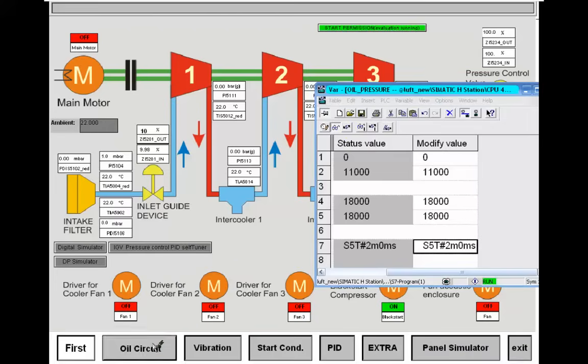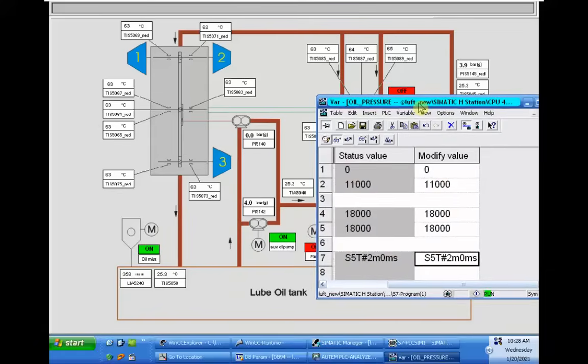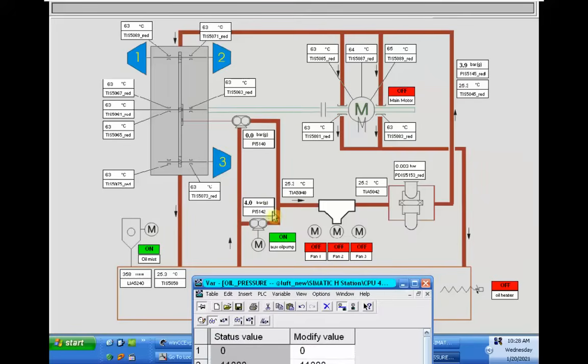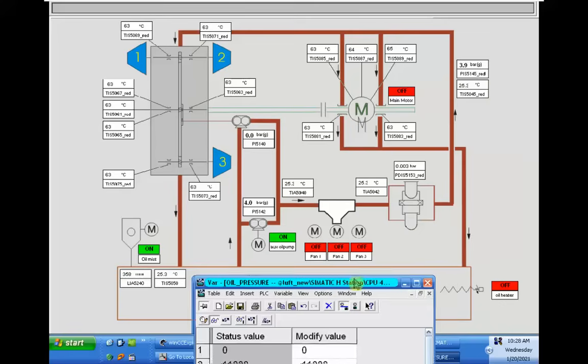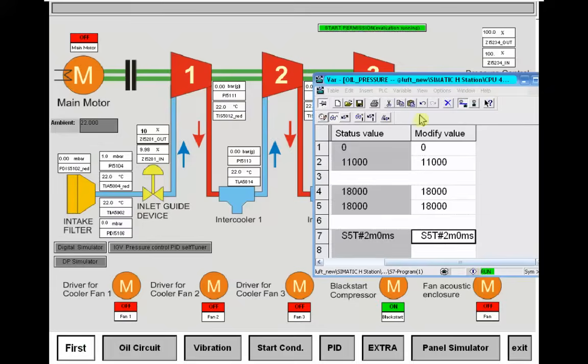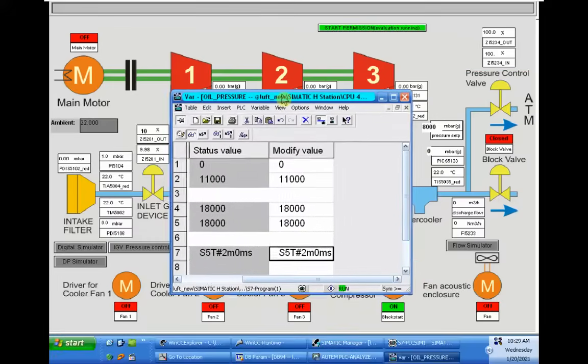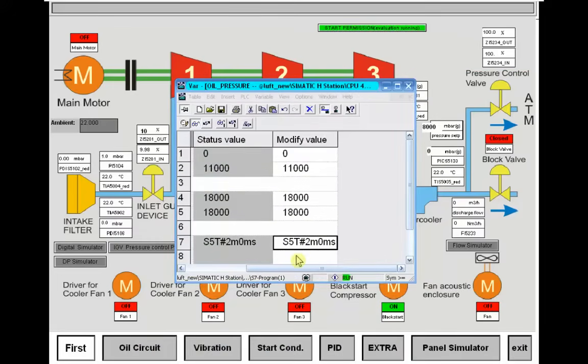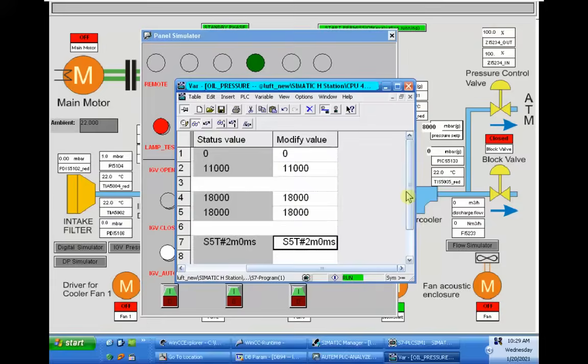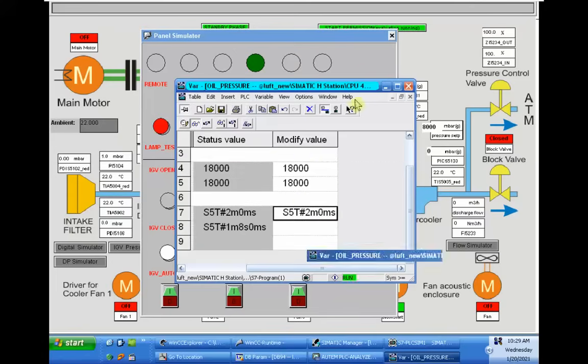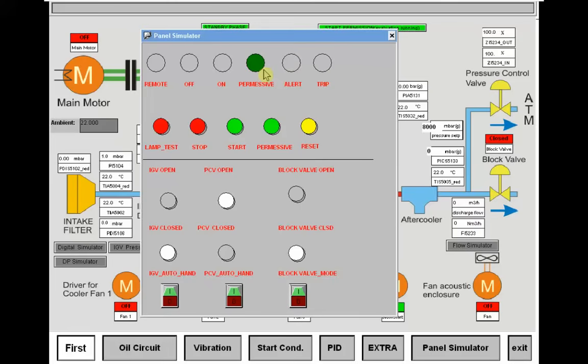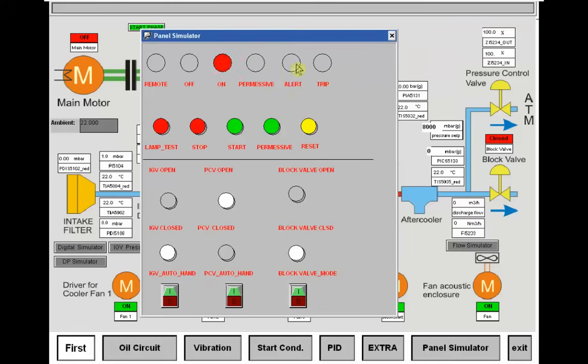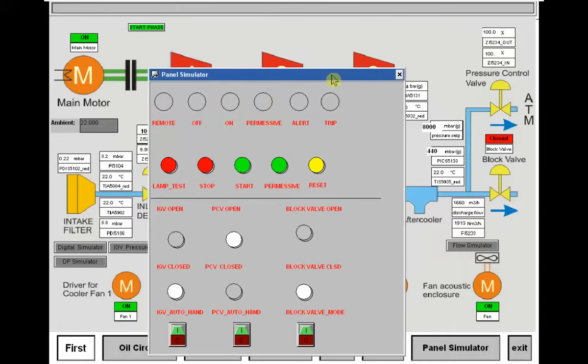Let's go and see what's happening here. We have the oil pressure on the electrical side and the main header oil is also available. The oil condition is met for oil pressure, so the permission will be okay. After the permission timer expires, it's now possible to start. You can see that we are in the start phase.